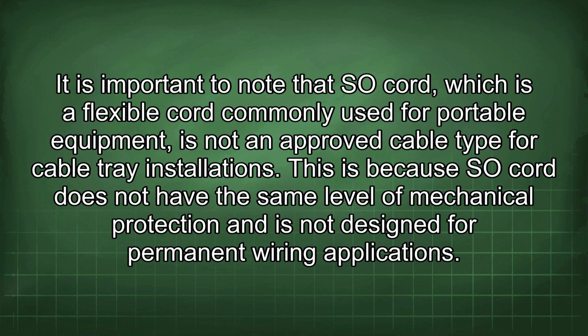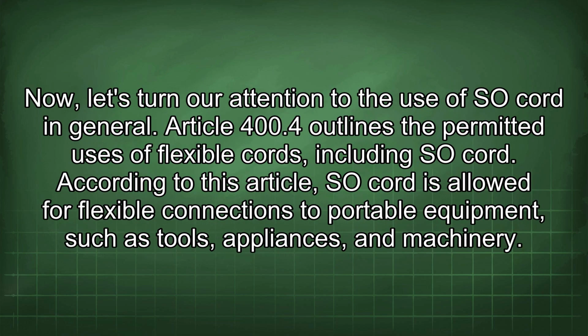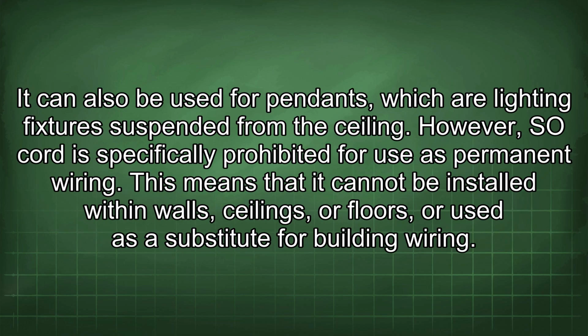This is because SO cord does not have the same level of mechanical protection and is not designed for permanent wiring applications. Now let's turn our attention to the use of SO cord in general. Article 400.4 outlines the permitted uses of flexible cords, including SO cord. According to this article, SO cord is allowed for flexible connections to portable equipment such as tools, appliances, and machinery. It can also be used for pendants, which are lighting fixtures suspended from the ceiling. However, SO cord is specifically prohibited for use as permanent wiring. This means that it cannot be installed within walls, ceilings, or floors, or used as a substitute for building wiring.